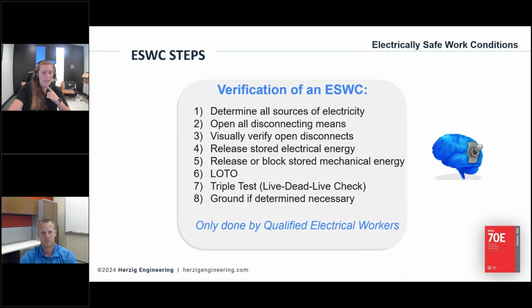Okay, to summarize, here are those 8 steps. Determine all sources, turn off your equipment, and then open all disconnects. Release stored electrical energy, release or block stored mechanical energy, apply your lockout tagout, do your live dead live check with your meter or with another device, and ground if determined necessary. Again, this is only going to be done by qualified electrical workers for 50 volts and above. And I did have a question here, is the cutoff the same for AC and DC? And as of this version of the 70E, yes. So it's 50 volts across the board.